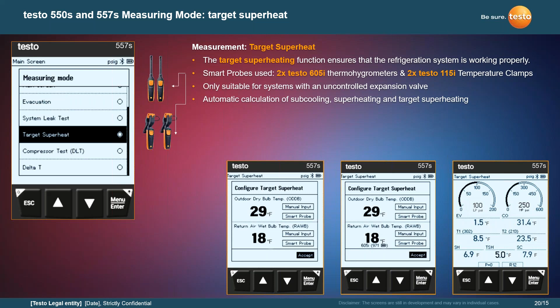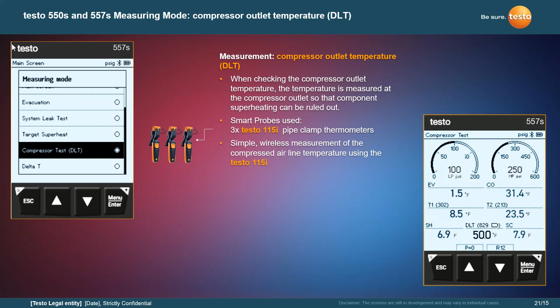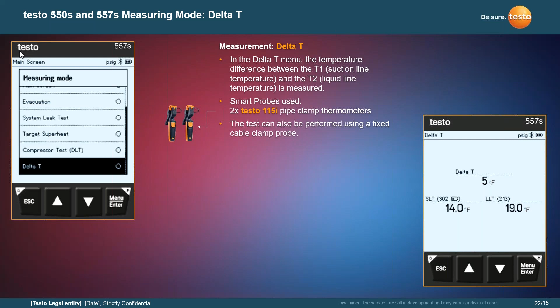And then we also have the compressor outlet temperature or compressor test. Checking the compressor outlet, you're going to use 3 of the pipe clamps, 1 at the outlet of the compressor, so we can rule out any superheating or anything of that nature. You can use both wired or the wireless pipe clamps here. Of course, with the wired, you'd only be able to use 2. You definitely need at least 1 Bluetooth pipe clamp as well. And you can also do your delta T between T1 and T2 to see where you're at. And sometimes, looking at heat pumps, there are some rules of thumb that you're going to look at based on delta T.